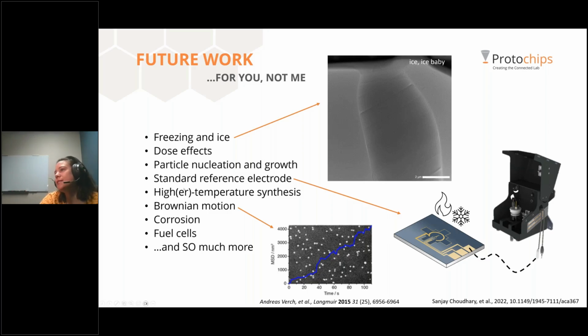I did not mention this, the standard reference electrode, but it is an important consideration. First off, even taking the standard reference electrode out of the equation, how does the temperature affect your reference potential on the chip? I would imagine that there is an effect, that there's some sort of potential shift, but I don't know what that would be. But then also, if you're using our standard reference electrode where we have this metal bridge in between the two, if you're heating at the tip, but you're not heating at your electrode, I would imagine that there would also be a potential shift between that, but someone would need to study that to confirm it.